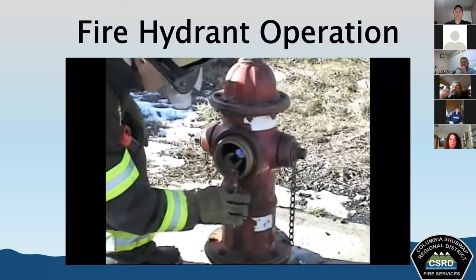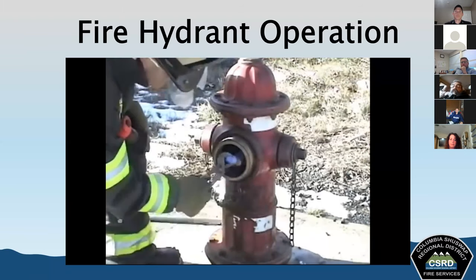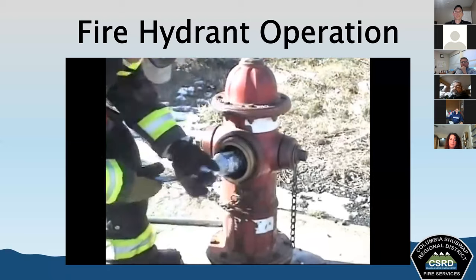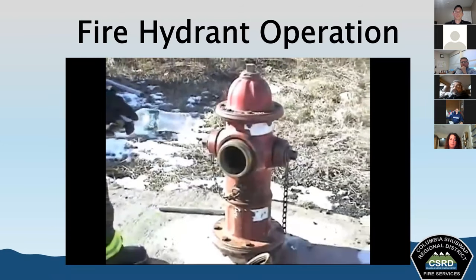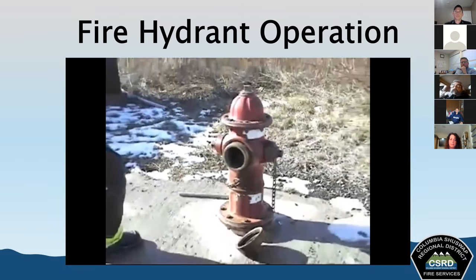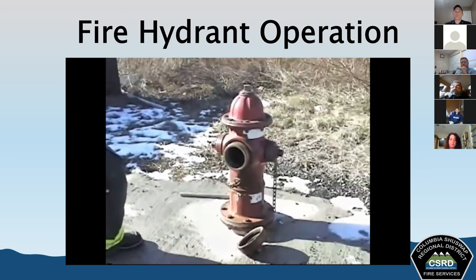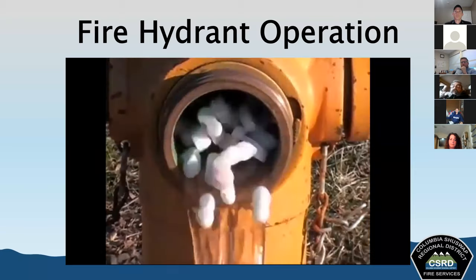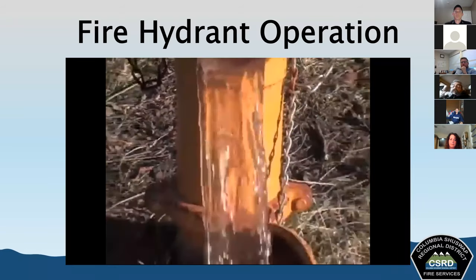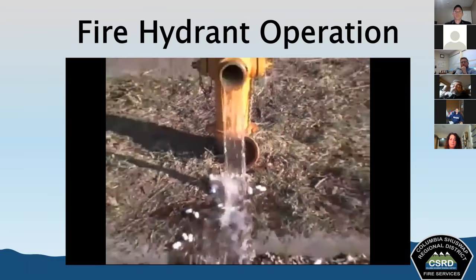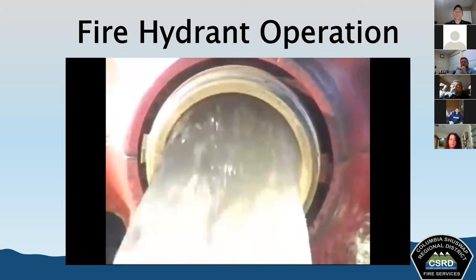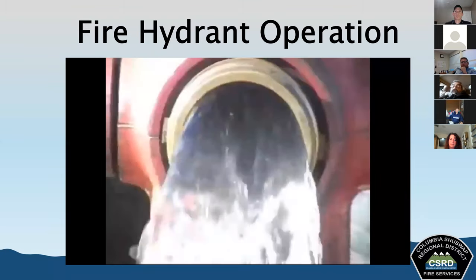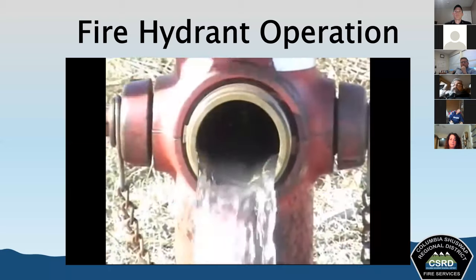Never reach into a hydrant with bare hands. Use a tool and gloved hand to carefully extract any large obstructions. To clear smaller waste from the barrel, open the hydrant slowly. The force of the water will lift the trash up the barrel and out of the steamer opening. Opening a hydrant quickly may trap garbage at the top of the barrel, keeping it from being expelled.